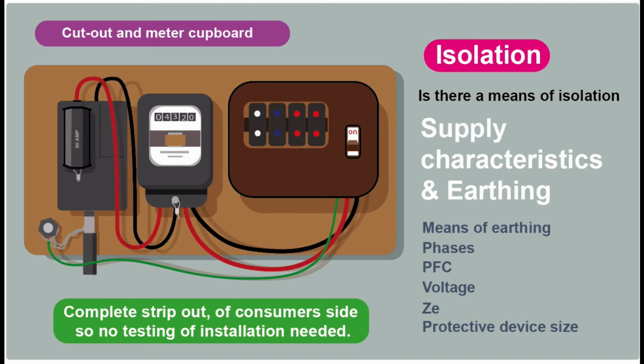Right, we're keen to start work. So the first thing we do is have a look in the fuse board cupboard, where we'll find the fuse board, the meter and the service cutout. There's no point testing anything after the consumer unit. That's all getting ripped out. We're getting a new board, all new cables. No point testing any of that.